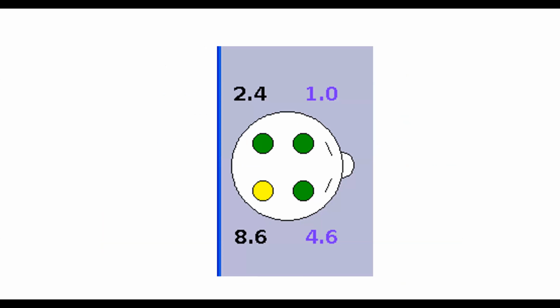The second thing that people need to troubleshoot is the impedance. So is the impedance value less than 10? You can oftentimes have issues with your tracing when the electrodes are not well attached. This is especially important when you're using the standalone devices that don't have a very sophisticated amplifier or a head box where you plug the electrodes in. Impedance tends to be less of an issue as you're starting to use more of the full EEGs that have really great amplifiers and filters on them. But for aEEG standalone simple amplifiers, we need to have a very clean signal to be able to get a good quality tracing.